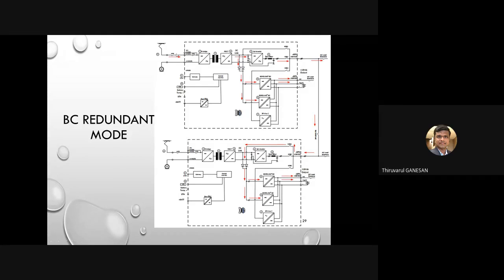For example, this is a main catenary. Through the main catenary, it will convert DC to AC, AC to DC, and here it is a three-phase inverter. It will feed coach one and two auxiliary loads, and it will convert 415 volt to 110 volt to charge the battery system. Similarly, this line will feed coach three and four battery charger via this contactor, and charge the battery of coaches three and four. Since the main catenary is not available, it will instead be fed through the coach one and two battery charging system. This is called redundant mode.